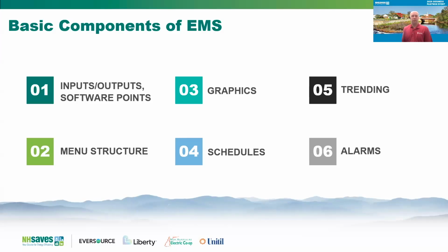But just know that if you have a modernized, fully functioning control system, you really should be able to easily manipulate your schedules for all your equipment. You should be able to enable trending for all points with relative ease. And you should be able to have alarms for major systems like freeze stats and other issues that should pop up and cause attention from a maintenance and operations standpoint.